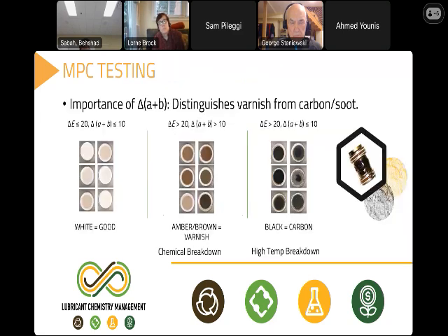Just quickly speaking here, we want this. This is chemistry breakdown. And when you see the dark patches like this, I'm going to say that's a mechanical or engineering related issue. This is carbon. This is from burning the oil into its hydrocarbon subcomponents. Okay. That's carbon. That carbon is below the range of filtration. It's under 0.1 micron pharmaceutical grade, because I've used the 0.1 micron pharmaceutical grade filters and it doesn't remove it. Okay. The only way to remove that material is electrostatics.